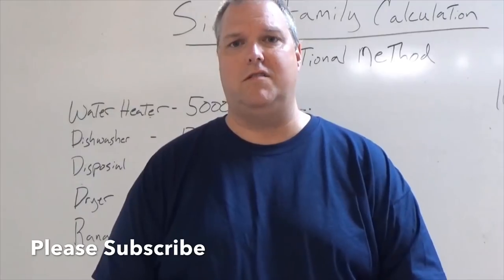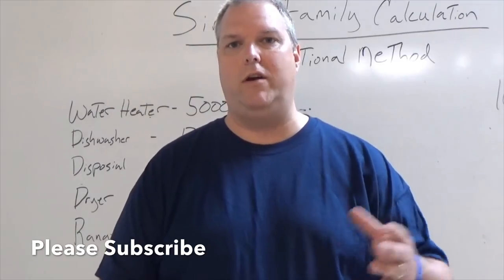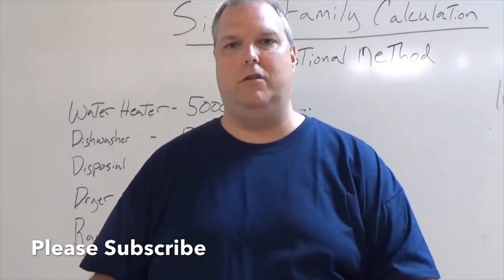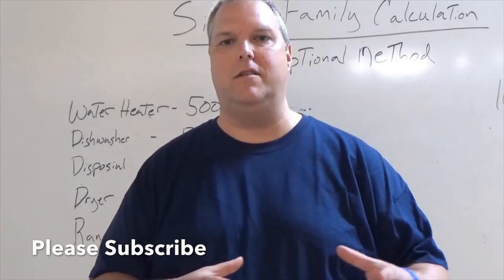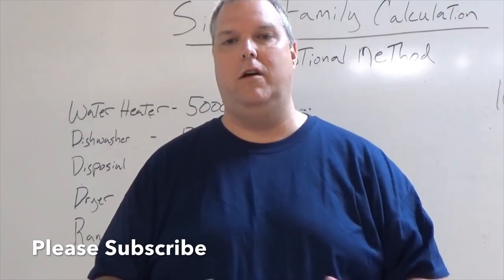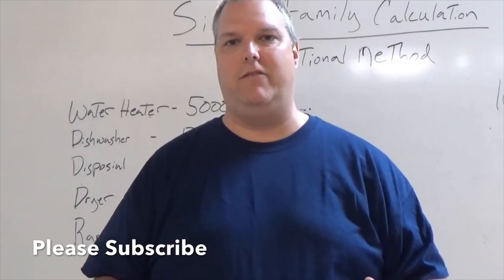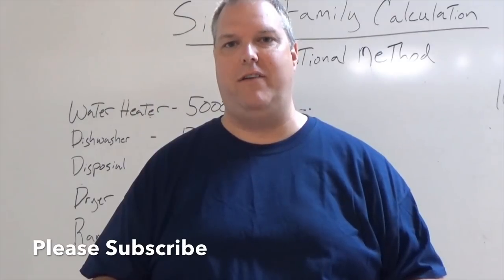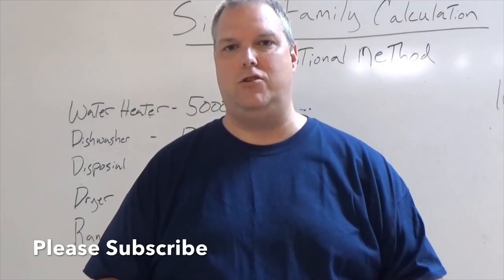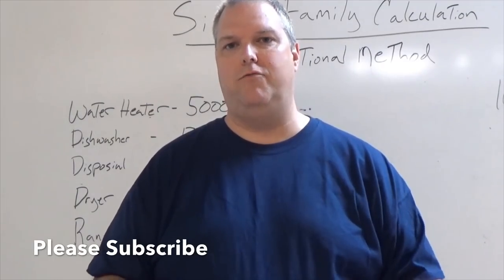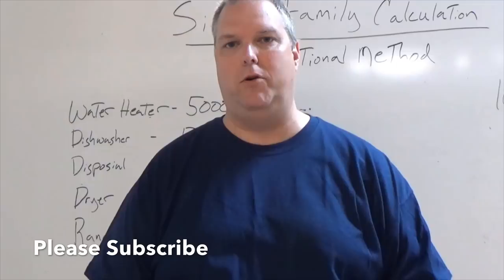In the standard method, after finding general lighting we move to fixed appliances as a separate step. In the optional method, we incorporate fixed appliances directly into the demand load calculation. We don't call it the general lighting load — we're adding everything together and then applying a different demand factor. You'll want to use NEC article 220.82 and follow through subsections B and C, which break down what goes into this part of the calculation.